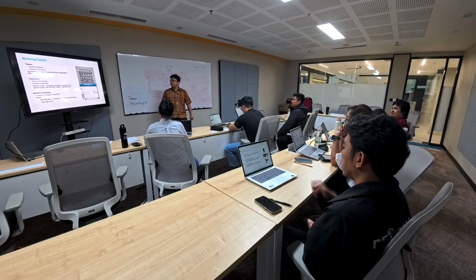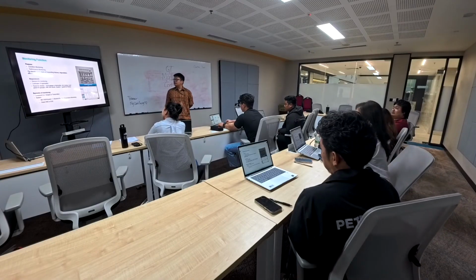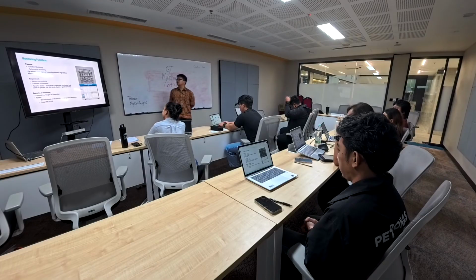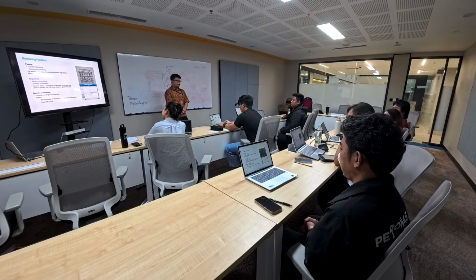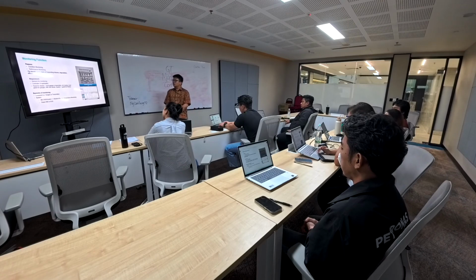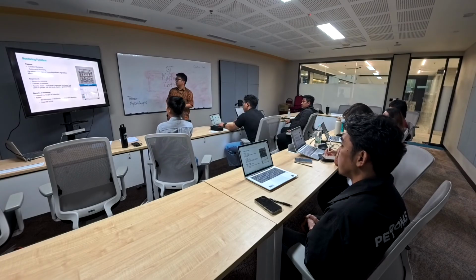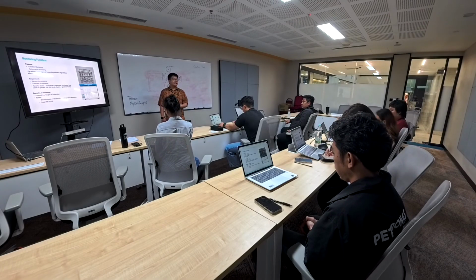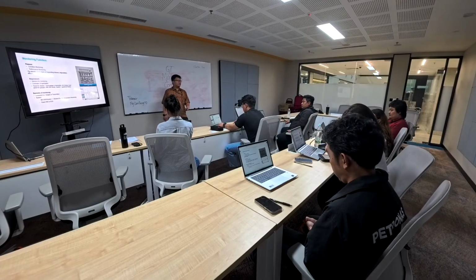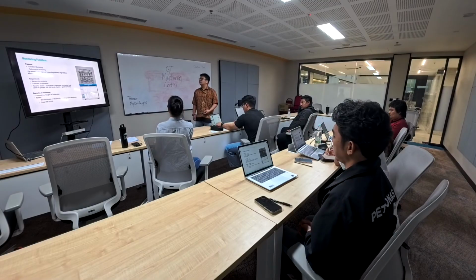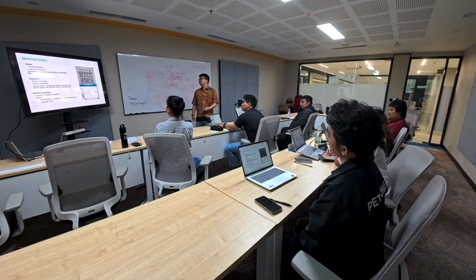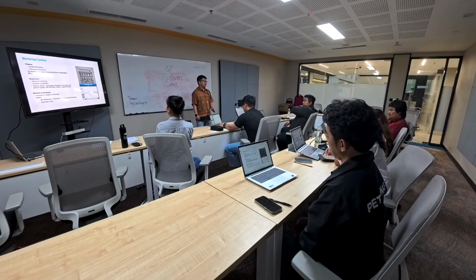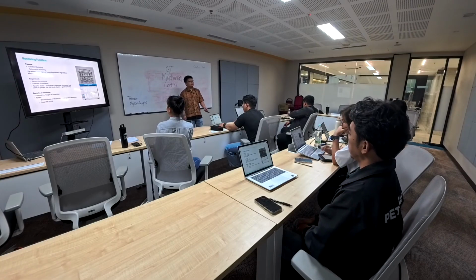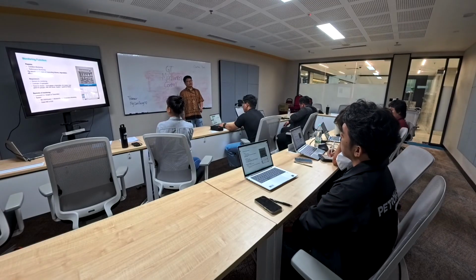So we move to the monitoring function. What's the purpose of it? To identify early signals of engine failures, degradation, and also efficiency issues. As it says, it is purely for monitoring. So we will have our local gauge or transmitter. It will also have a display. You have a sensor. Sometimes you have a controller, sometimes you don't. But normally you will have a panel or display. That display can be in the form of a local gauge, can be in the form of an LCD, which is like a transmitter, or it can also be wired to your DCS or your TCP for monitoring.